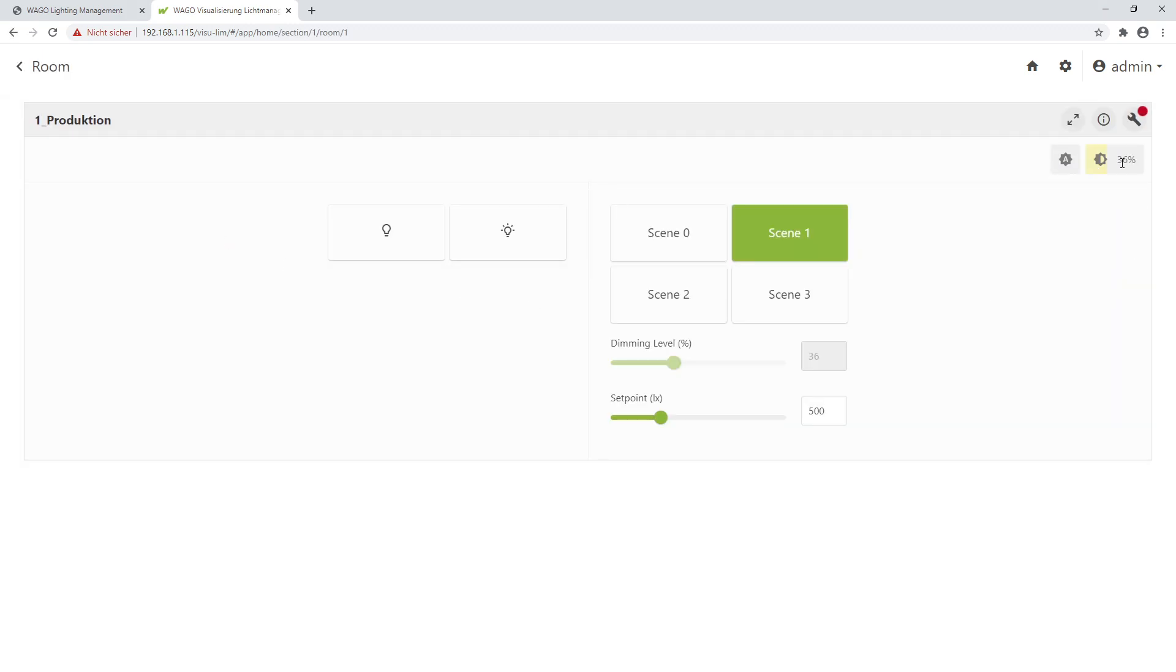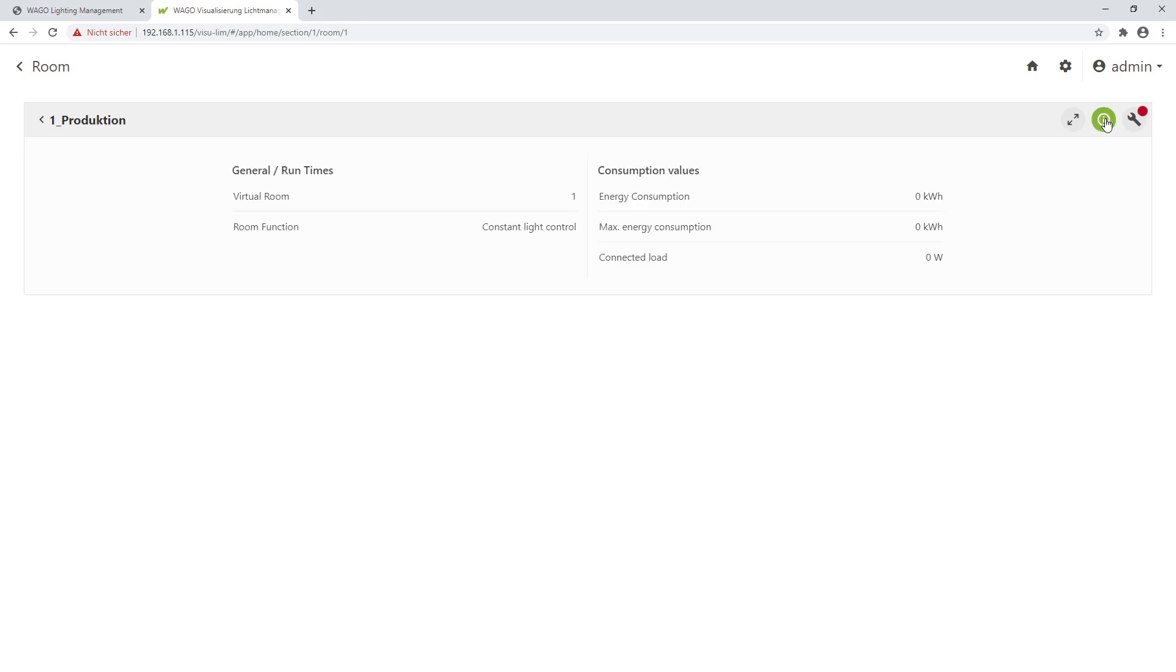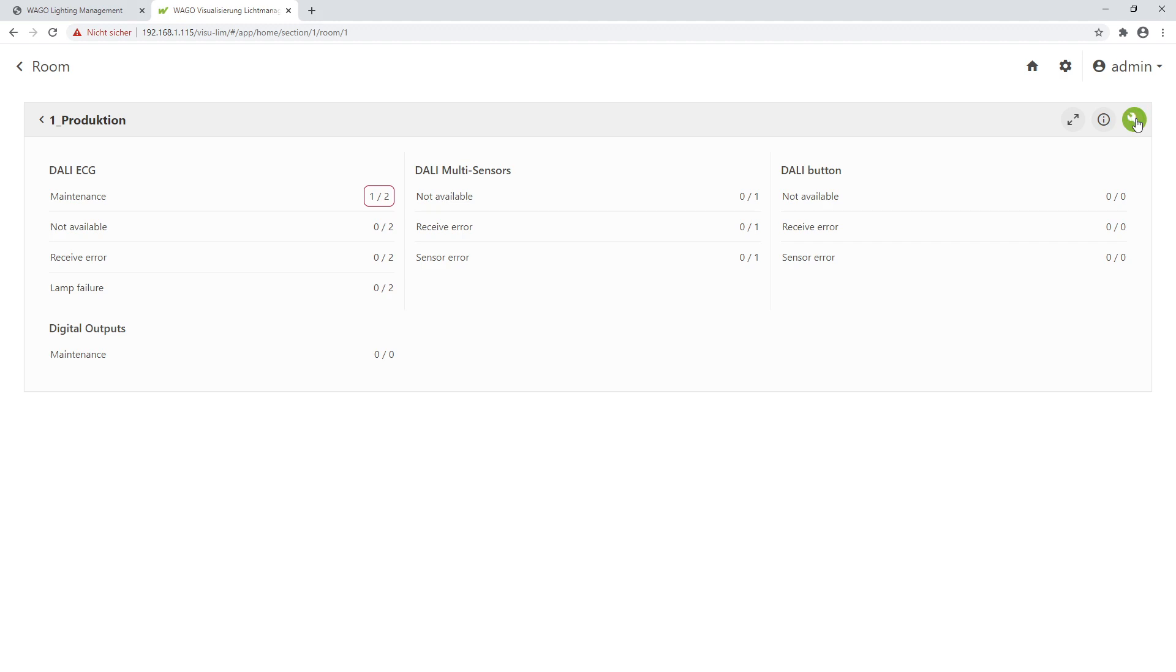Here you can get the status information, change to full mode, or click on this eye to get more information about this room. For example, which room function is used, how high the energy consumption is. You see there a red dot is flashing, and this shows you that it has something to do with maintenance. I see now I get the message one of two DALI ECGs needs maintenance. For example, the operating hours is greater than the maximum.